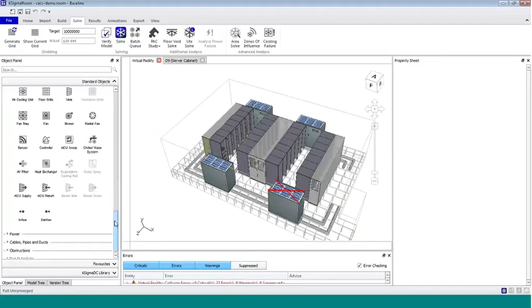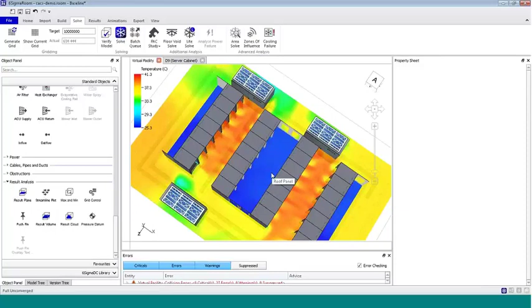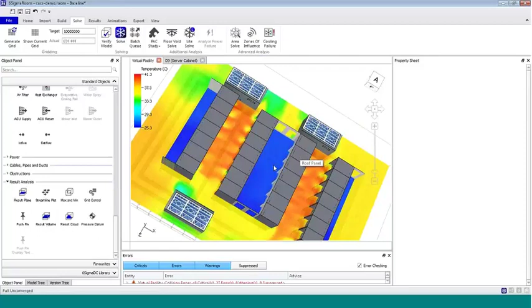As I mentioned before, under standard objects, if you go down to results, you can drag and drop the result plane to create it. With cold aisle containment, you'd expect the air temperature inside the aisle to be consistent or close to the supply temperature from the grills, because there's very little infiltration, provided the cabinets are well sealed, or there's enough airflow to match the IT equipment.